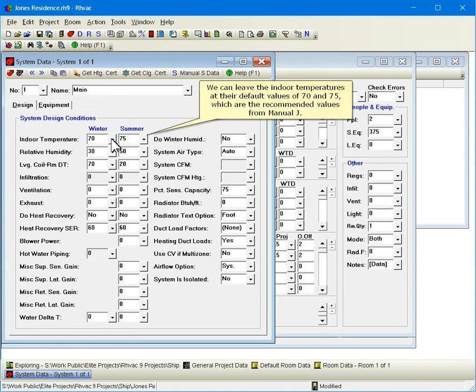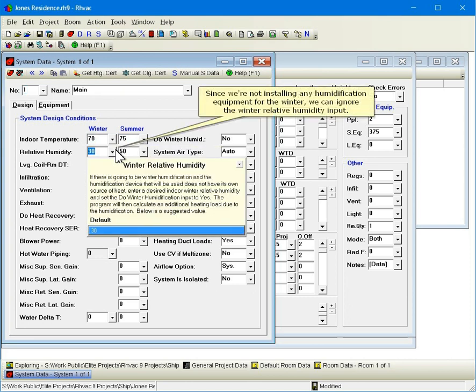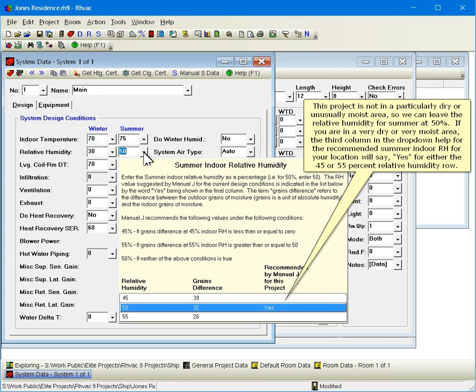We can leave the indoor temperatures at their default values of 70 and 75, which are the recommended values for manual J. Since we're not installing any humidification equipment for the winter, we can ignore the winter relative humidity input.